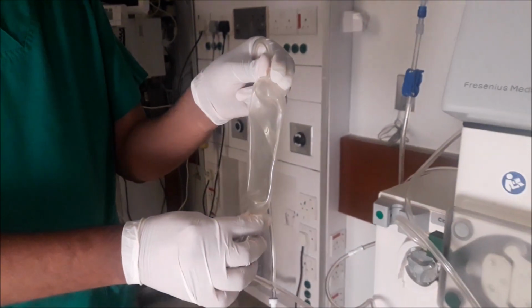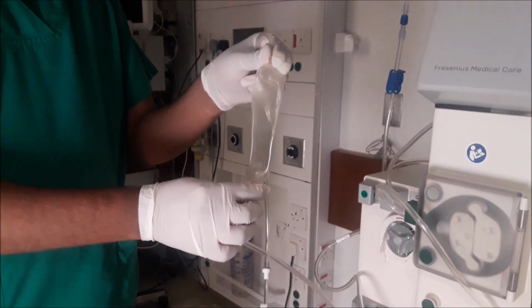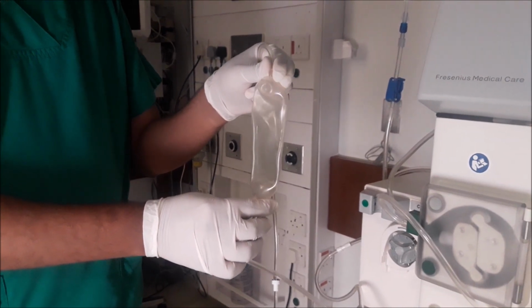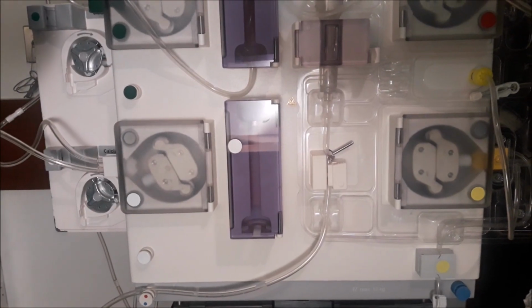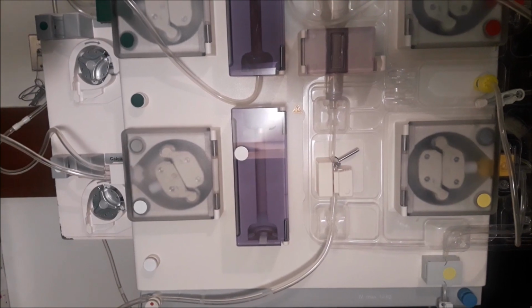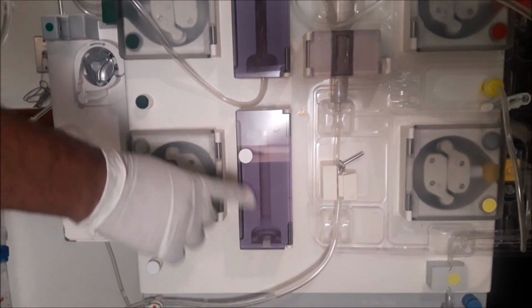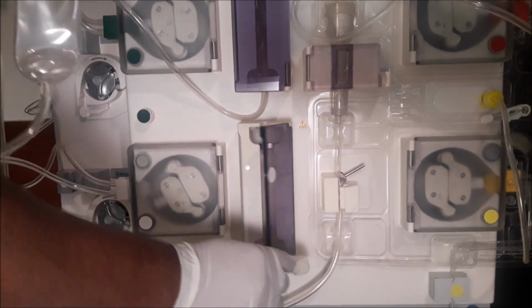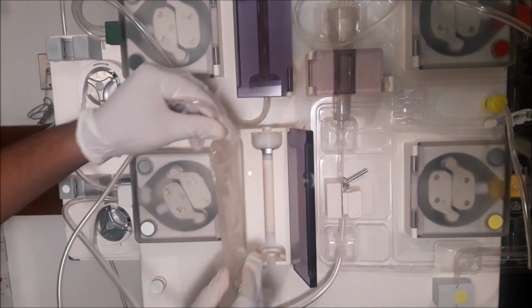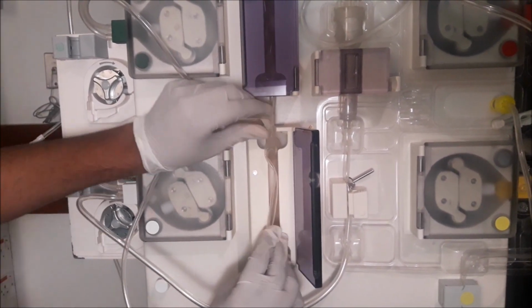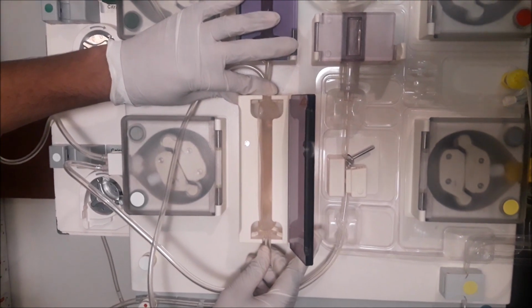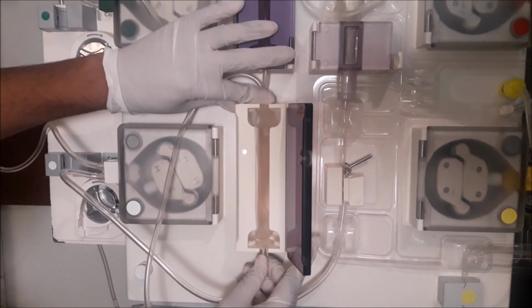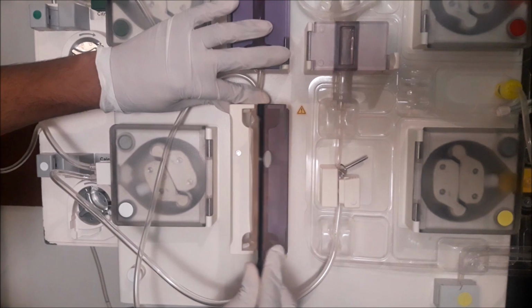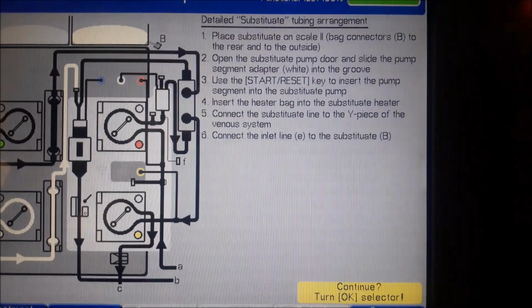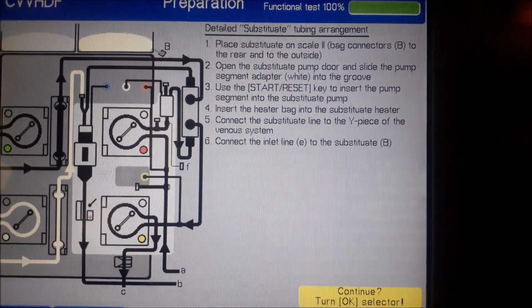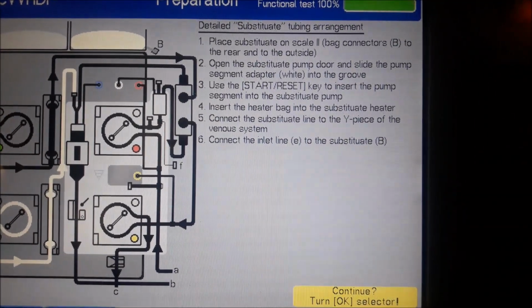This is the substitute bag which is always present with the substitute tubing. Let's put the substitute heater bag into the substitute heater. Open the door and insert the bag. Now the substitute bag has been inserted. Close the door. Point number 5 is connect the substitute line to the Y piece of the venous system.